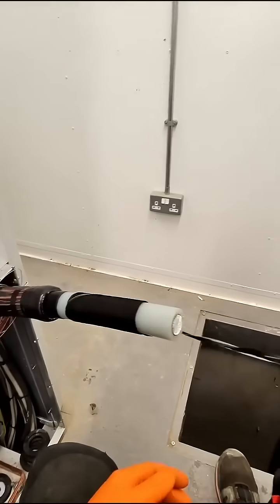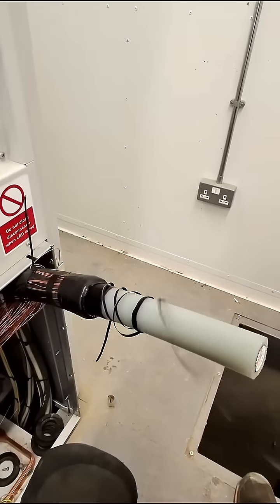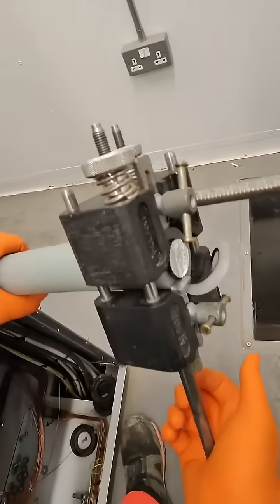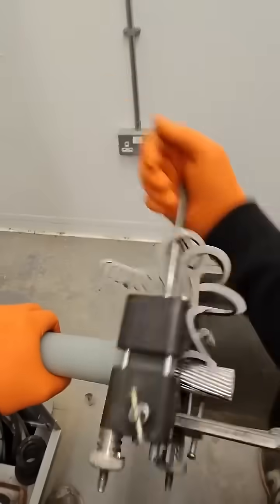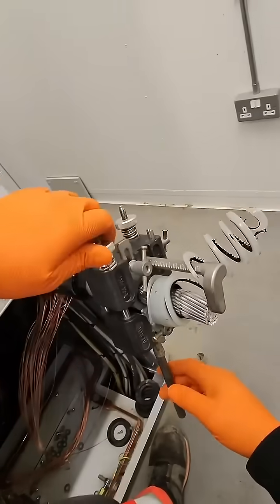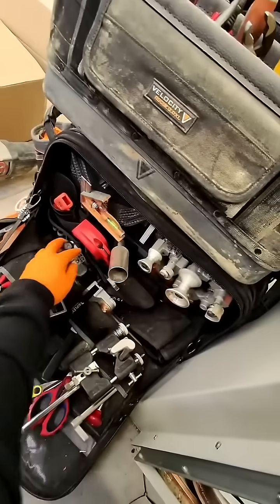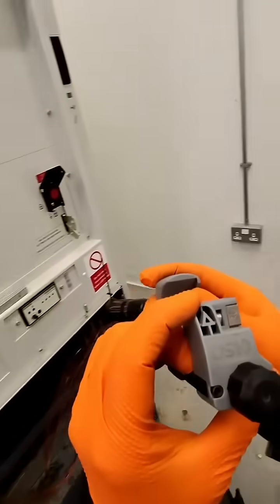Tie it off and sand it, then remove the strippings. Now remove the primary insulation with the Alrock LH-02, set this to the depth of the lug, and remove strippings and tool. Now add a small chamfer with the Ripley US-10 — a lovely compact tool.